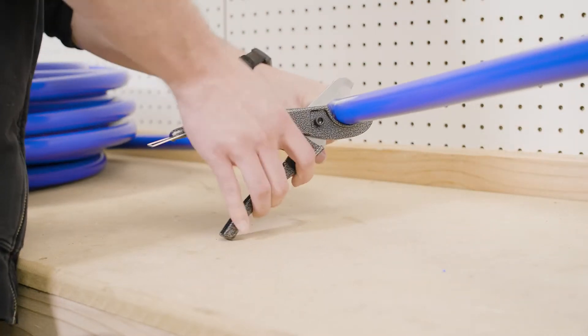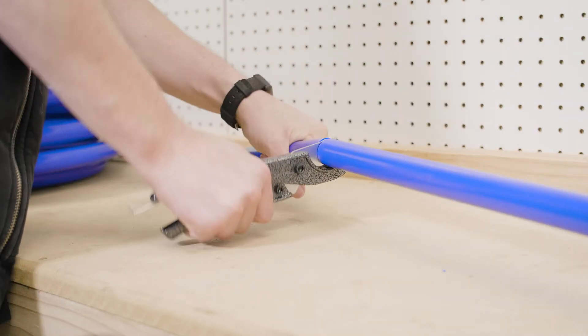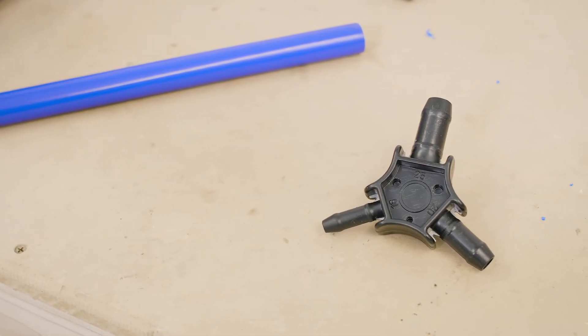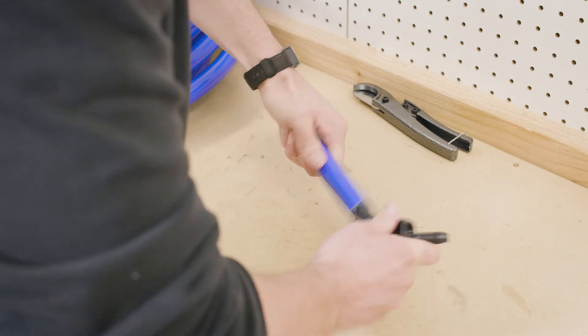Using the tubing cutter, rotate the cutter to ensure a square cut. Insert the three-quarter inch portion of the deburring tool into the tube and rotate approximately three times to deburr the tubing.